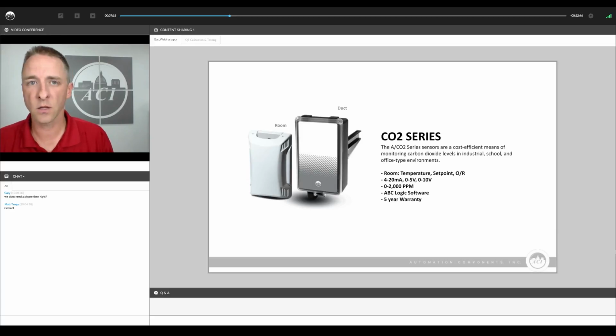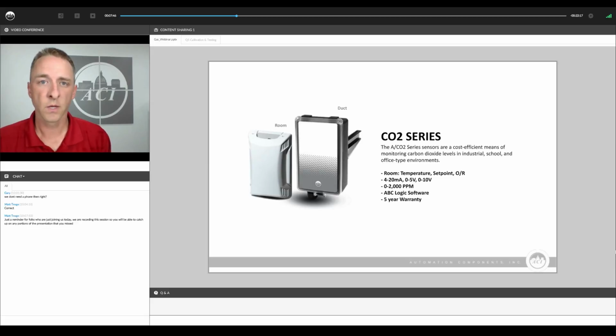This is a patented technology, so there are only a few licensees of this patent. There are a lot of other competing technologies out there. Some use what's known as dual wavelength, where it basically uses two infrared beams inside of the CO2 sensor. While that is somewhat effective in reducing the drift, it does not eliminate the need for periodic recalibration. So the ABC logic software is the only feature in CO2 sensors that eliminates the need for periodic recalibration while maintaining an accurate CO2 output.